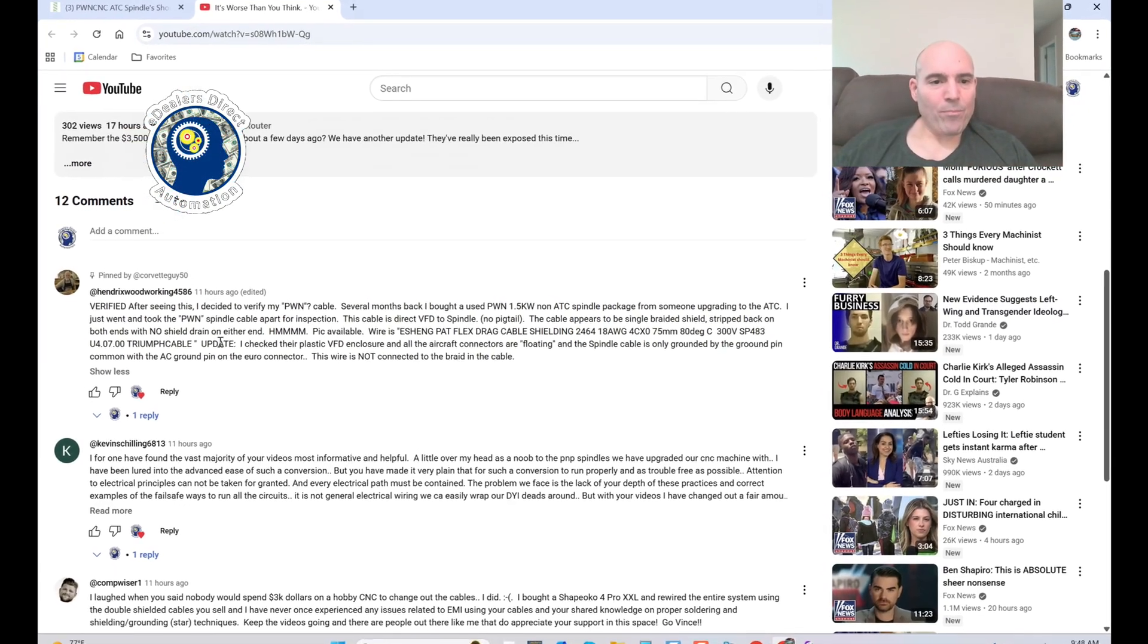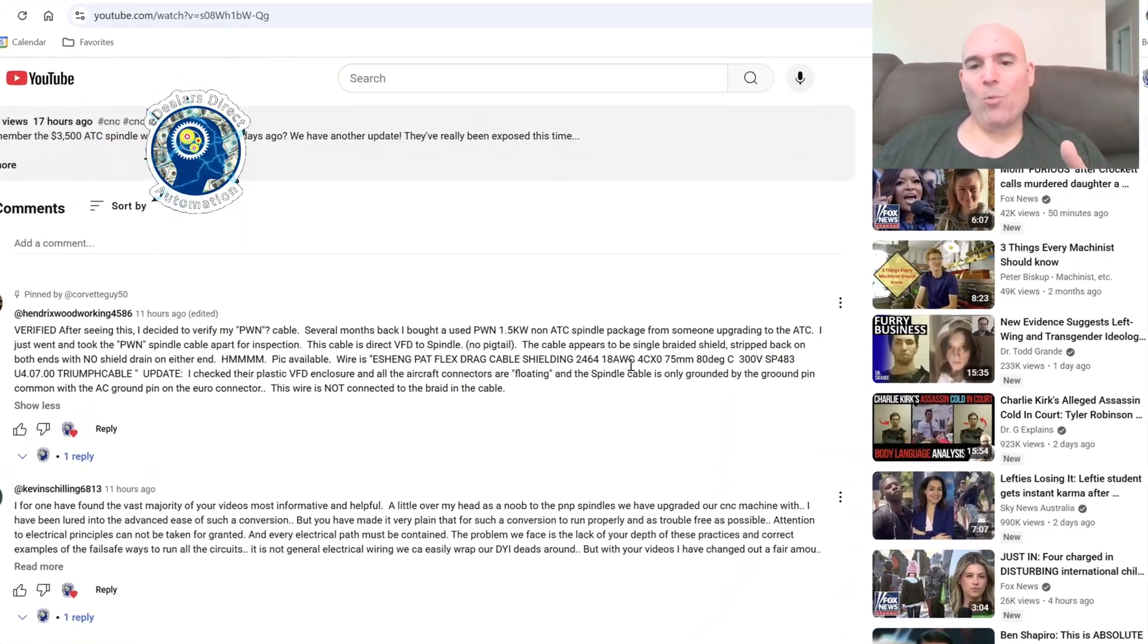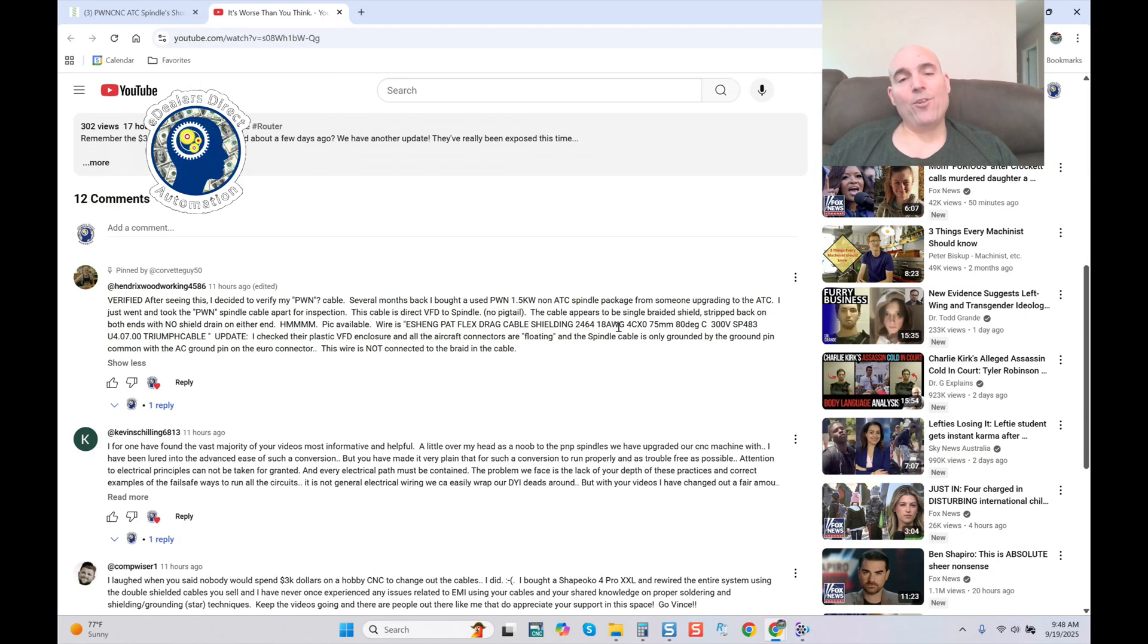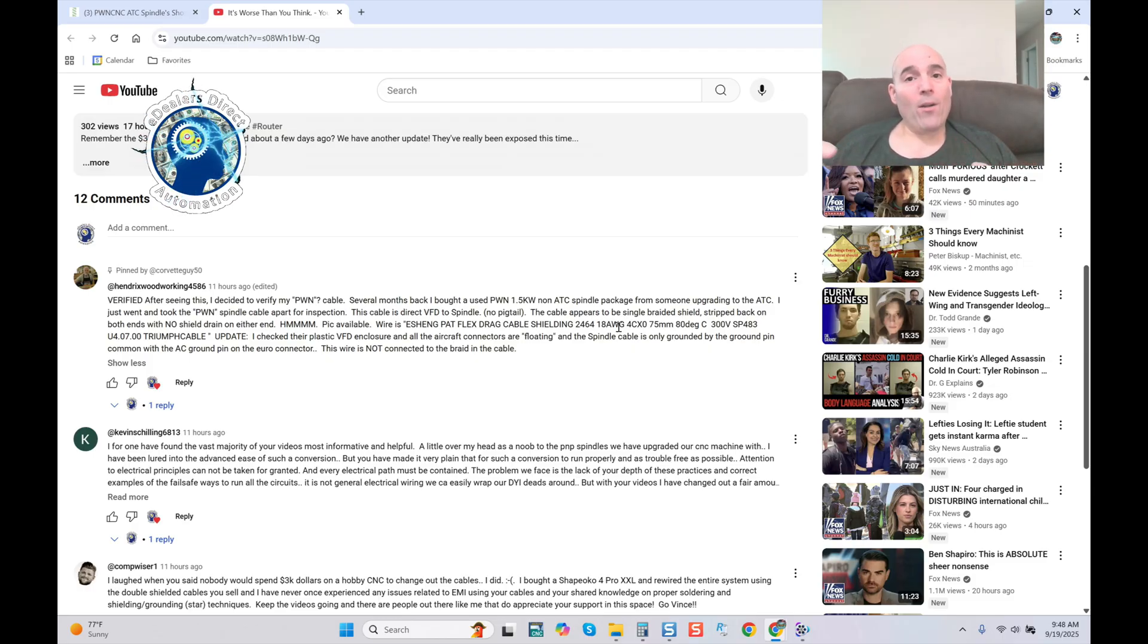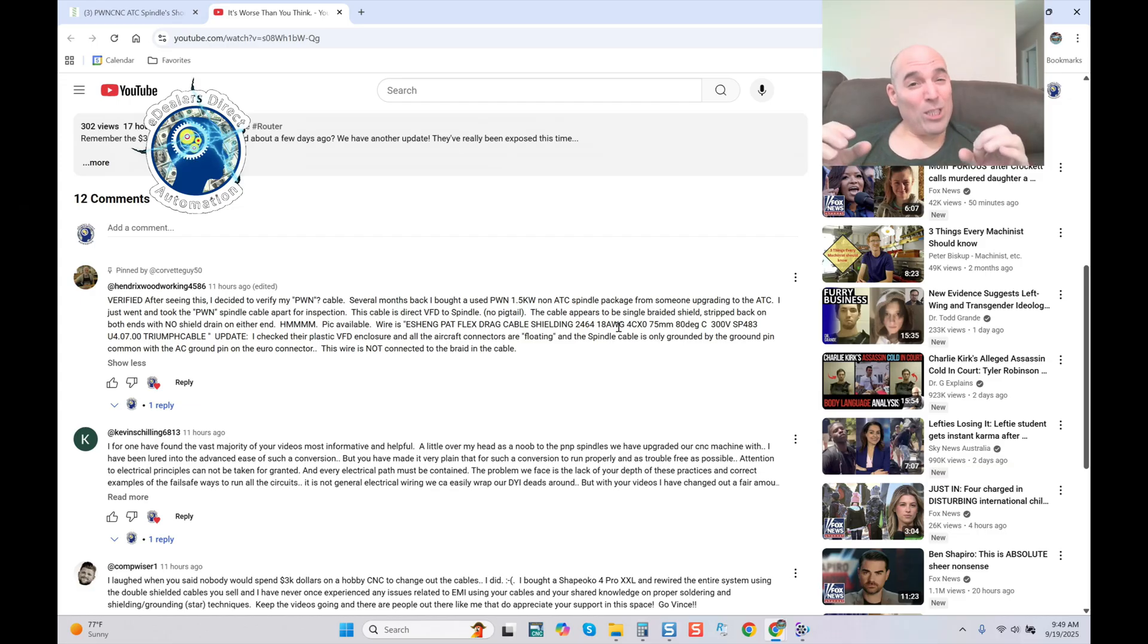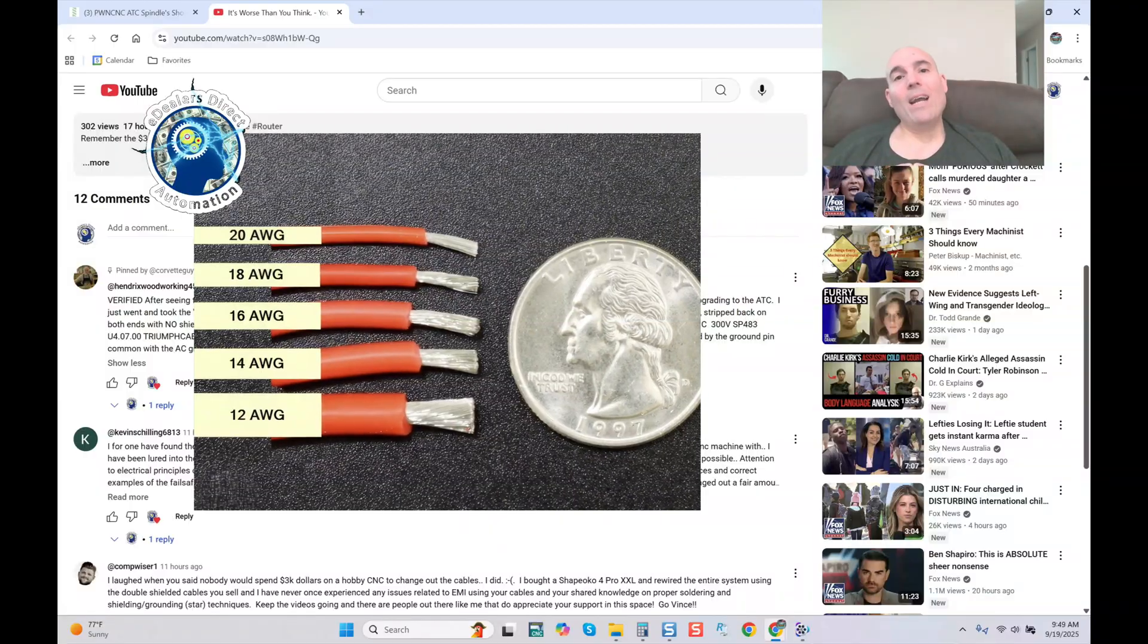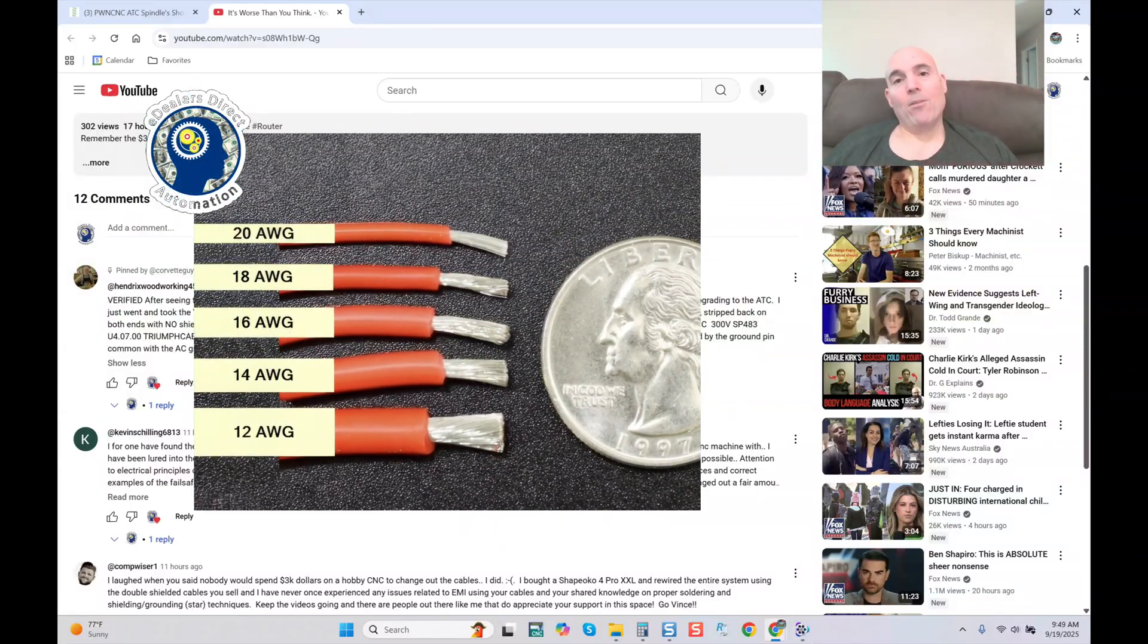Pic available. Wire is—and he goes into detail about the wire that's used, meaning the cable. It's 18 gauge. Now guys, I never recommend using 18 gauge. Anyone that understands voltage drop understands the longer the cable is, the more voltage drop is present. Of course, lower gauge wires are always going to give you a better resistance to voltage drop simply because they're thicker.